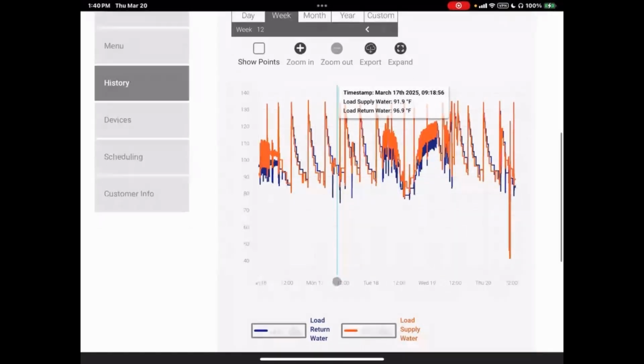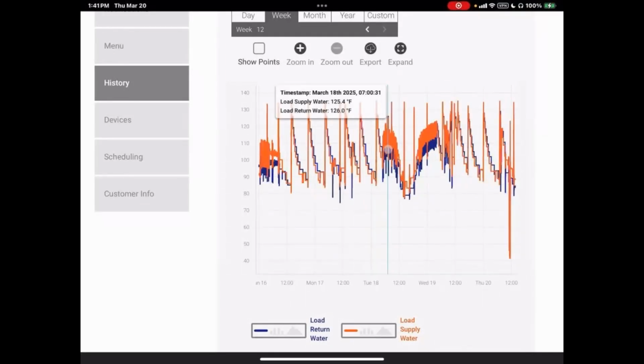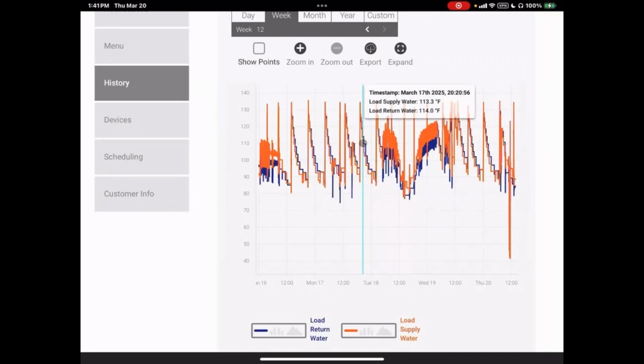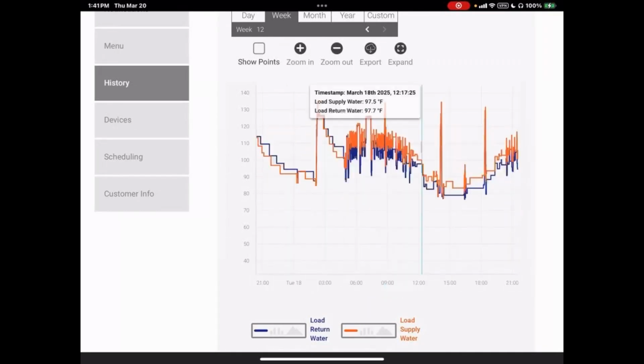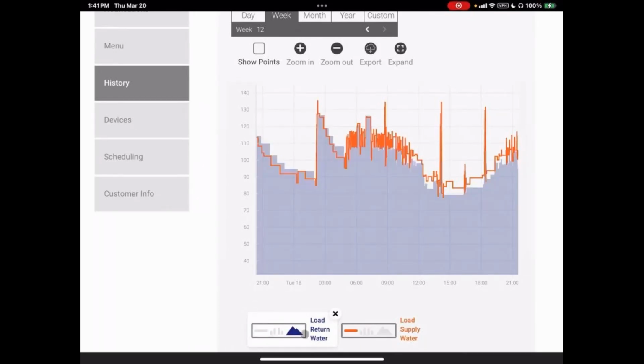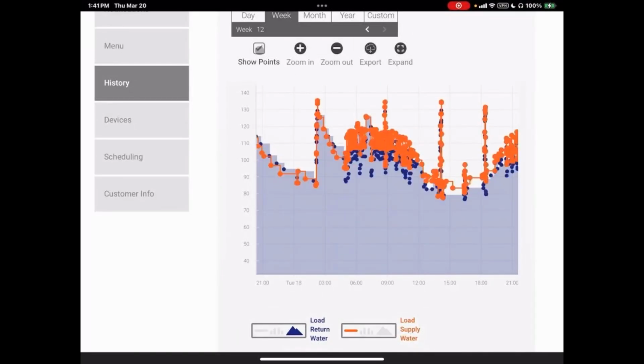But from here, as you can see, as I move my mouse across here, it'll drop a vertical line and then give me a timestamp and show me the actual numeric value for that moment. And if I wanted to highlight it on one section, you can actually highlight that, and then it will zoom us in on that one area so we can see a little bit more granular detail. We also have the ability to change the way that our graph looks. So I can put my return water as kind of this shaded in area. I can do things like show data points.